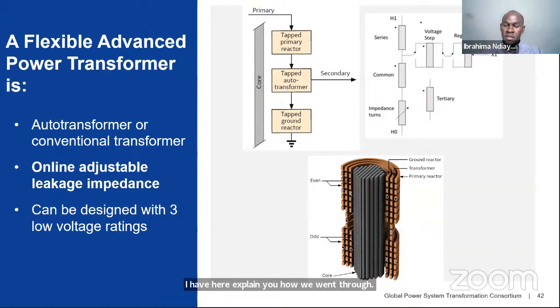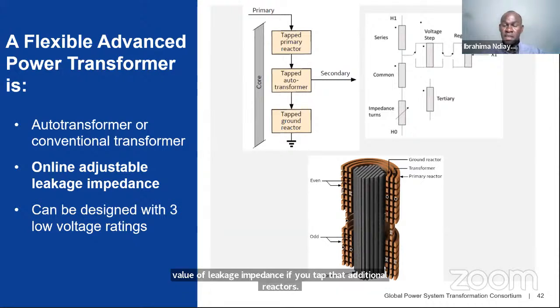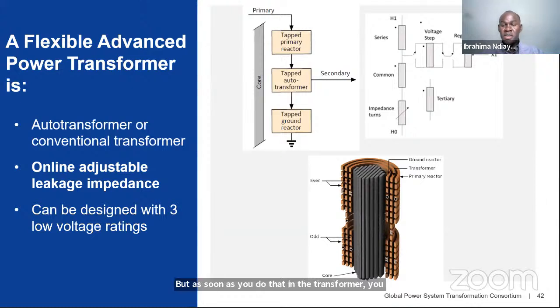Technically, if you can imagine a transformer being in series with reactors, you can easily see the reactors being part of the core of the transformer. If you put the reactor inside the transformer, you can still have different values of leakage impedance if you tap those additional reactors. But as soon as you do that in the transformer, you effectively change one of its most important parameters, which is the turn ratio or voltage ratio.